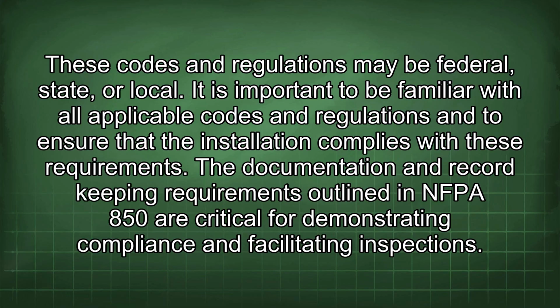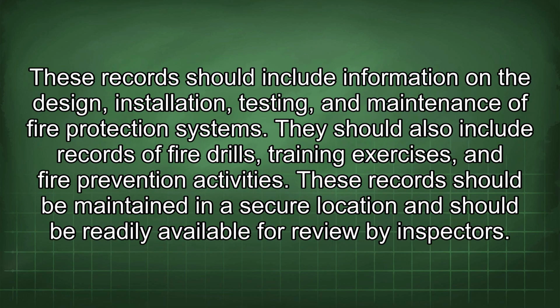these requirements. The documentation and record-keeping requirements outlined in NFPA 850 are critical for demonstrating compliance and facilitating inspections. These records should include information on the design, installation, testing, and maintenance of fire protection systems. They should also include records of fire drills, training exercises, and fire prevention activities. These records should be maintained in a secure location and should be readily available for review by inspectors.